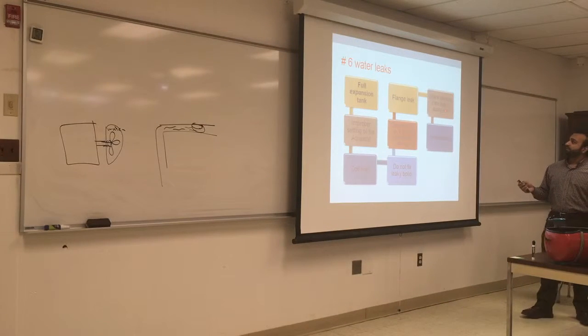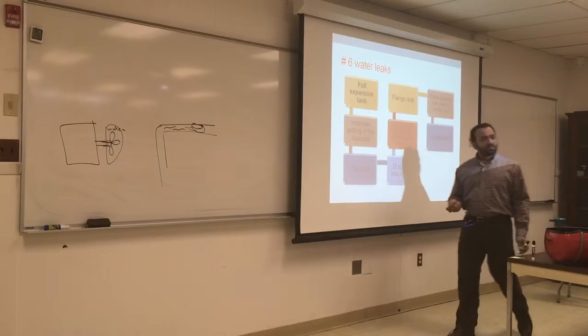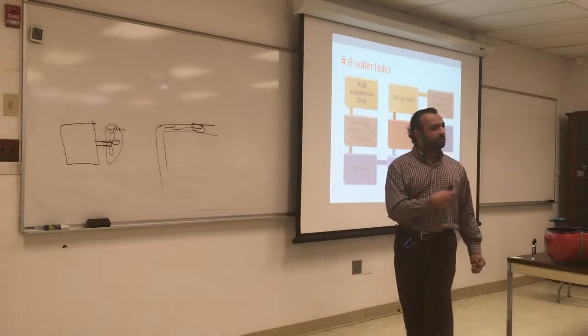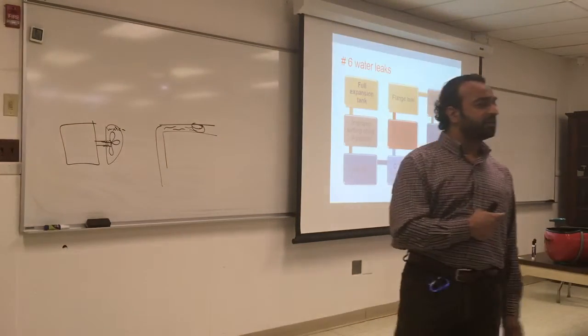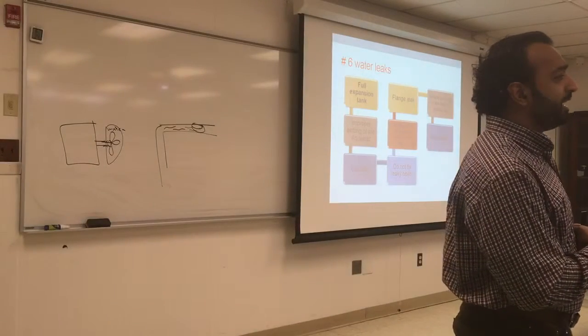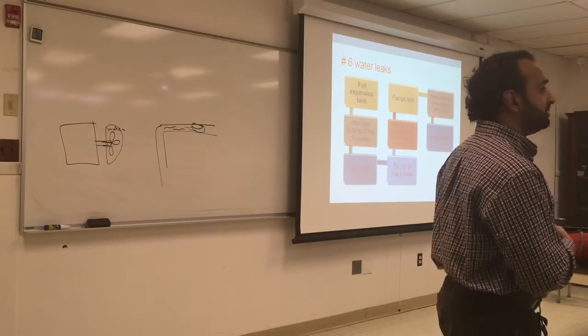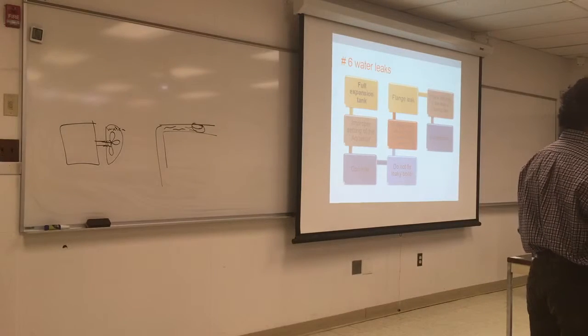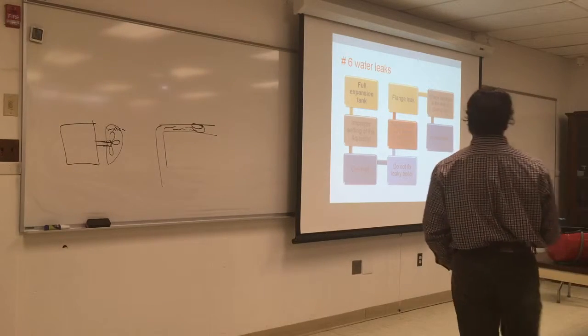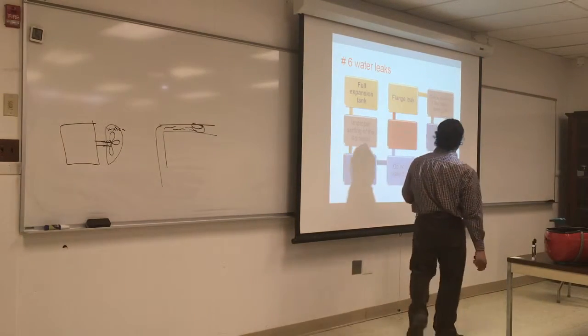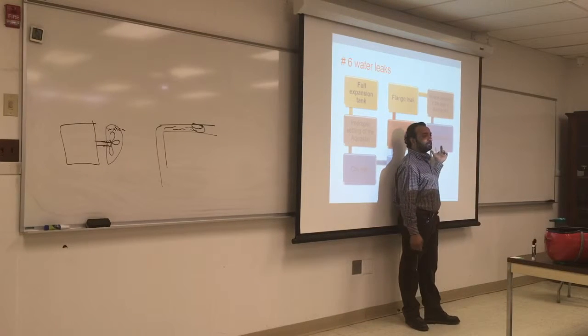Check the chimney if the leak is during the rain. If your system starts to leak, a lot of people neglect that part. Maybe your chimney is not covered properly. Maybe your chimney has some condensation. So make sure that the leak actually is coming from the boiler and the pipe, and not from the chimney. Condensation. When will we have condensation in the chimney? That's a very important question. Too much steam going up here.